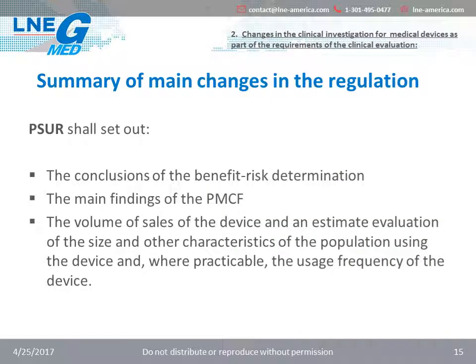PSUR, Periodic Safety Update Report, shall set out the following: the conclusions of the benefit risk determination. The second point, the main findings of the PMCF, post-market clinical follow-up. And finally, the volume of sales of the device and an estimate evaluation of the size and other characteristics of the population using the device, and where practicable, the usage frequency of the device.